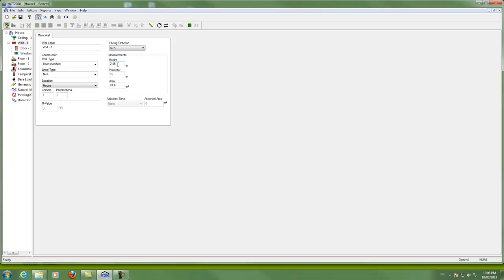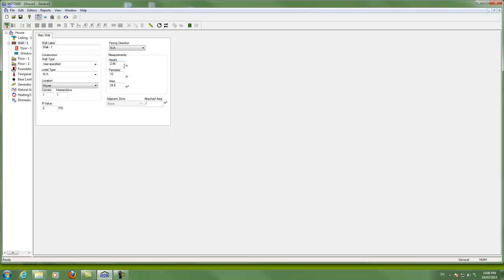So in the height you want to make sure that you count the joist, the floor joist area. Either on the floor below the wall you're doing or associated with the wall up above. But make sure you count it one way or the other. You can also count your floor joist space as its own wall type. That gives you the advantage that you can have a different R value for the floor joist area compared to the main wall area, which is usually the case.